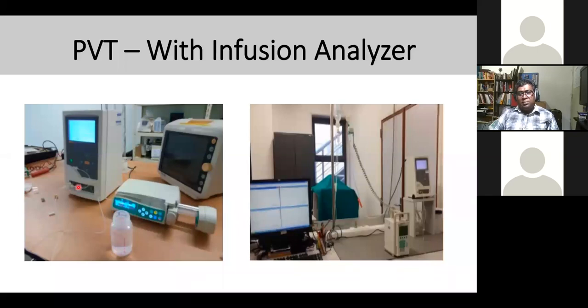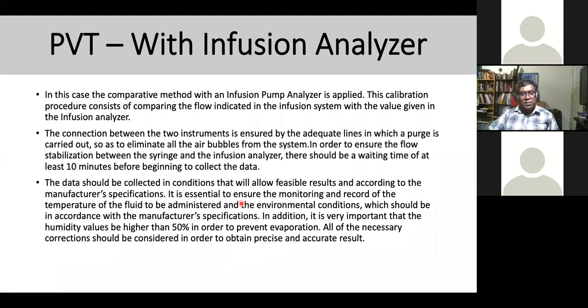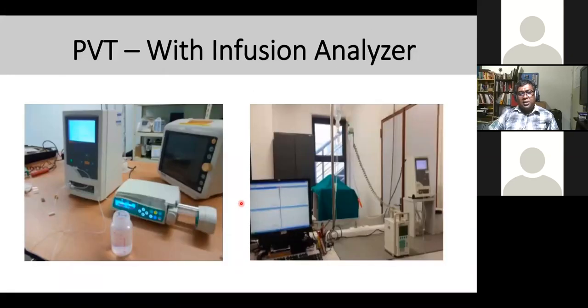Once you prime, there's fluid in the tubing. You're going to see the connection, and some reading popping out, but the reading should be near zero. Once you have primed the line, you're going to see the fluid going to the back, at the outlet of the infusion analyzer. Once done priming, you can start the setting.